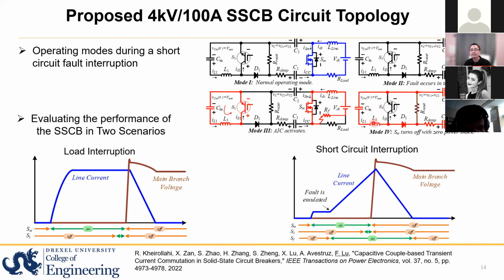Then we can see this inductor will flow through this loop, making sure that this reverse current exceeds the fault current. The working principle is similar, generating a reverse current to cancel the fault current. Once the current is higher than the fault current, this body diode turns on, and we have zero current switching. Then we turn this switch off, and everything ends.